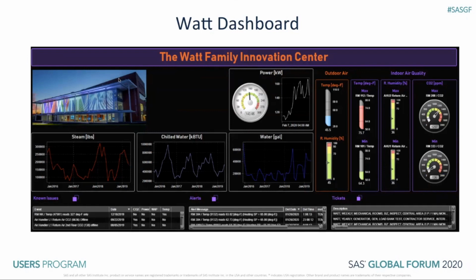We found that some of the CO2 sensors, a good example in the bottom right there, you'll see the CO2 sensor at 136. That's since been fixed. It was an issue with the CO2 sensor needing to be recalibrated, so we spoke with facilities, they came in and recalibrated the sensor.